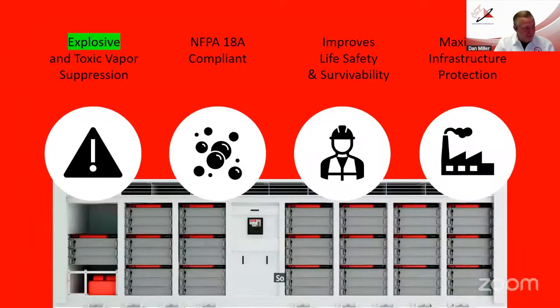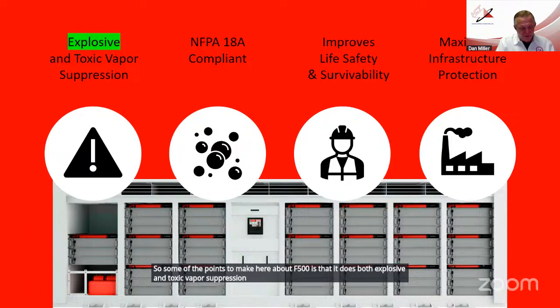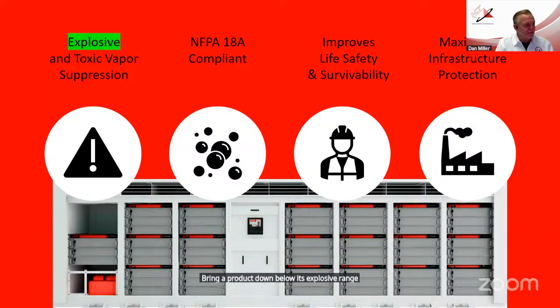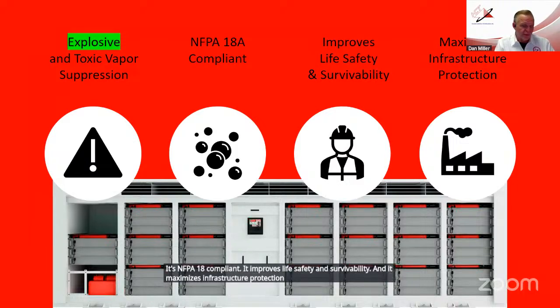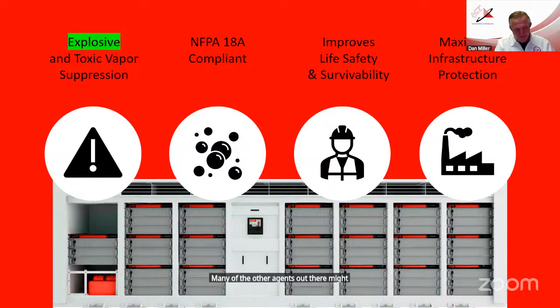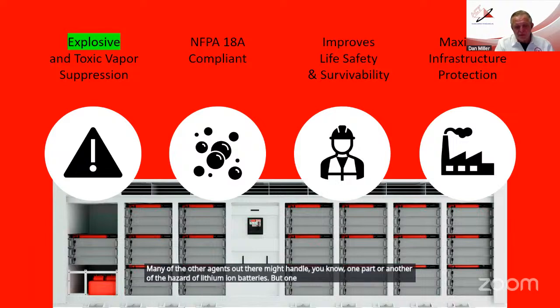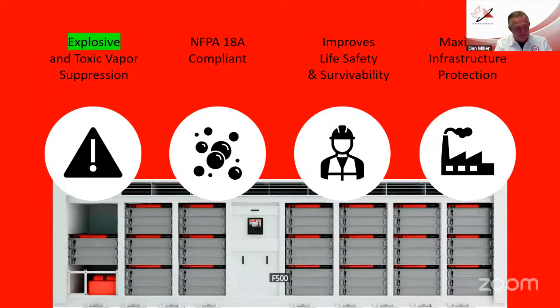So some points to make here: F500 does both explosive and toxic vapor suppression, and it's very prolific at that. As soon as it's applied at the right rate, it knocks those vapors down, brings a product below its explosive range, and enables survival. It's NFPA 18A compliant, it improves life safety and survivability, and it maximizes infrastructure protection too, because it's a great cooling agent. Many other agents out there might handle one part or another of the lithium-ion battery hazard, but one thing they struggle with compared to F500 is cooling and infrastructure protection. F500 really excels at that.